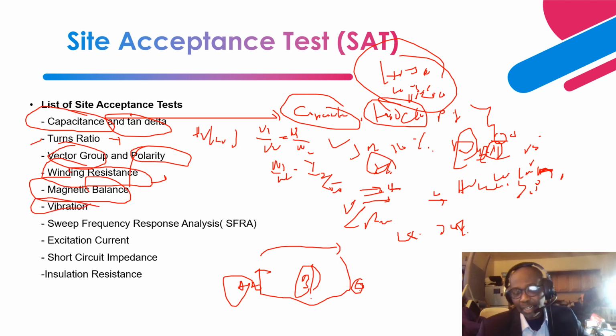Next is vibration, right? Okay, so the vibration, this is when the structural engineers come into play, right? To make sure that the transformer, whilst it's in operation, because of the active component, energization and all those things, creates vibration, right? And the foundation that the transformer sits on should be able to withstand this vibration throughout the whole life cycle of the transformer, right? So the structural engineers do all the testing to make sure, and also there's something they call natural resonance, right? They capture all the vibration signals to make sure that there is no natural frequency that will coincide with any other natural frequency to resonate and cause a breakdown of the foundation and any other structures in the transformer.